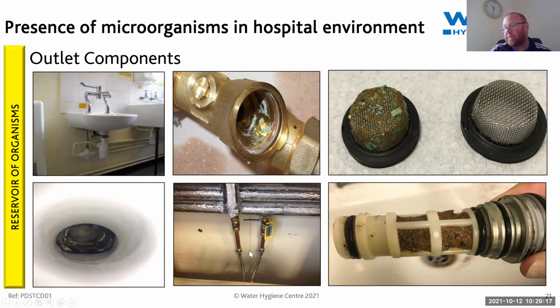We've got potential biofilm formation in the basin, in the drain point. So we need adequate drainage from the basin to ensure there's little area or potential for stagnation and biofilm development. We've got filters with some deposits here - could be flux, could be non-WRAS approved products.